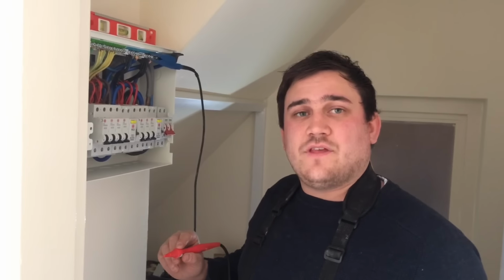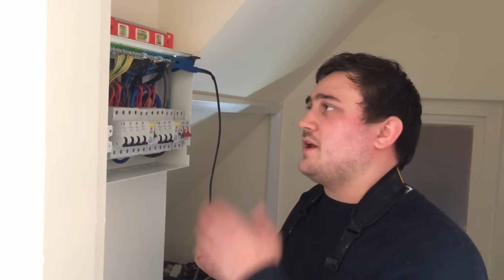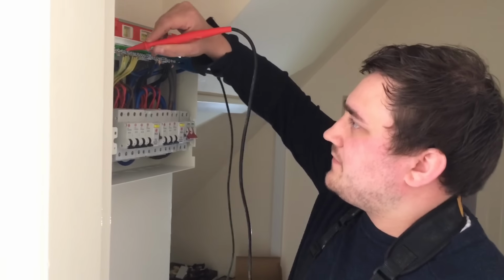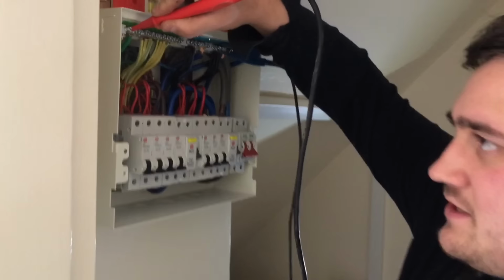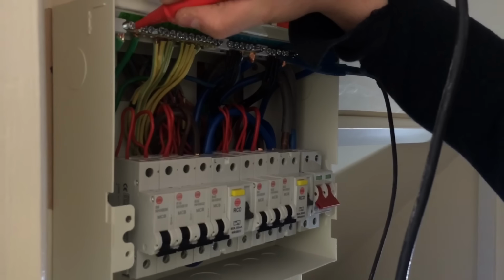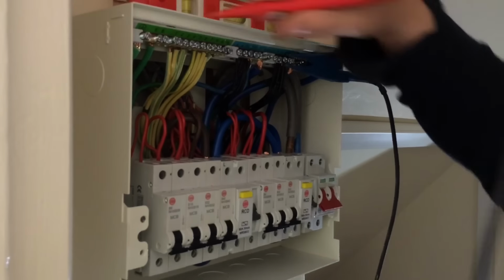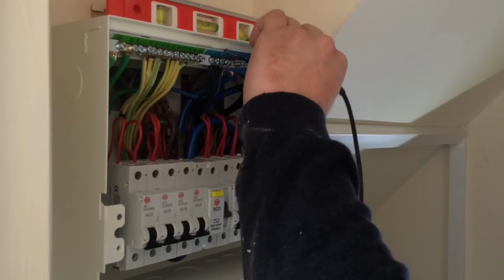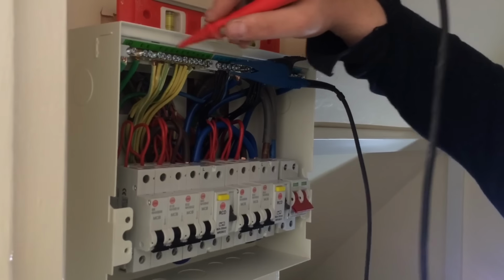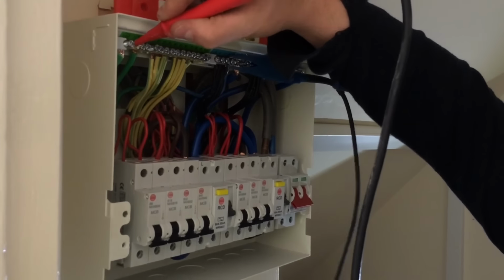We're now on the next part of the insulation resistance test. We're going to go between our neutral bars and our earth bar. So we're going to go on the first neutral bar for the first RCD. 500 megaohms. Second bar for our second RCD, and the earth bar, 500 megaohms also. We're now going to swap all the strappers around on the two-way lighting circuits and redo the insulation resistance to check that other side of the strapper.